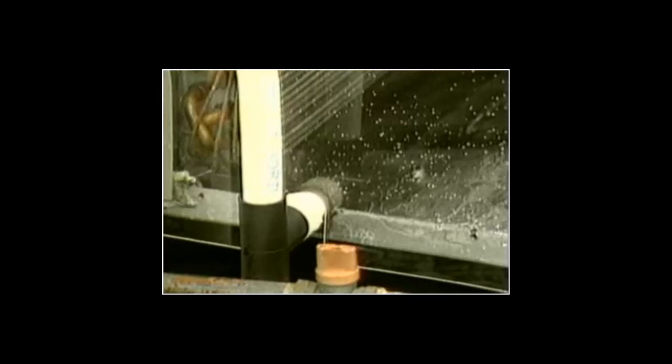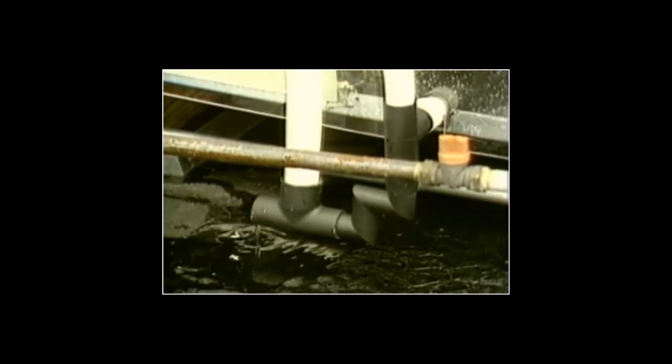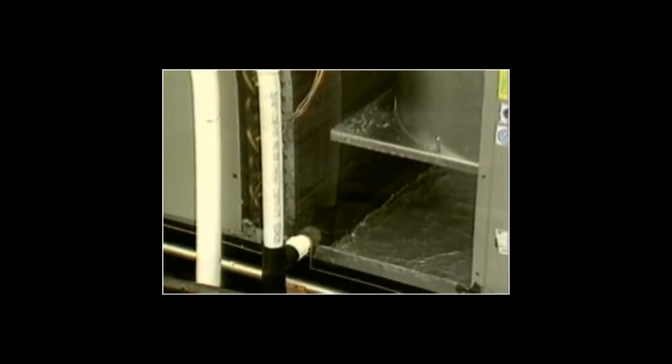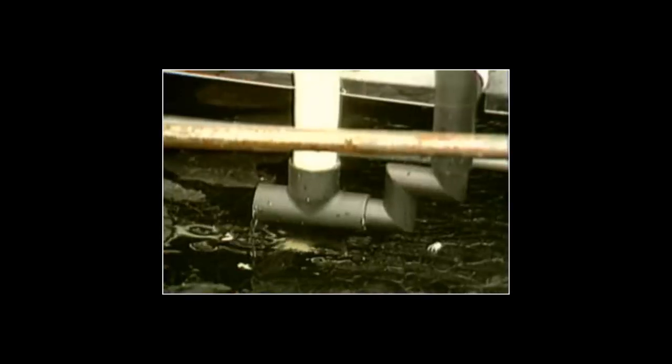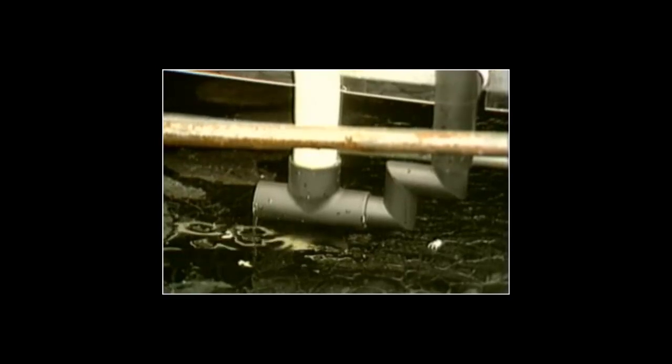With the aid of a transparent panel, the effectiveness of the CostGard condensate drain seal in preventing the blowing of condensate in a real system is shown here. Notice that condensate blowing stops as soon as the seal is in place and that condensate begins to flow. Now, with the transparent panel dry and the CostGard condensate drain seal installed, note that there is no condensate blowing and that condensate flows smoothly from the device.